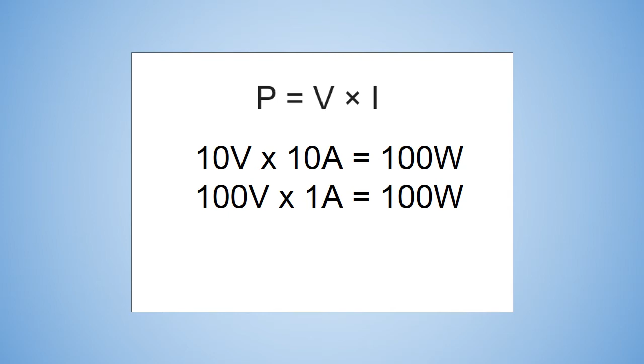But examine the V drop formula. A smaller current means a much smaller loss. Because current is a squared value, 1/10th the current means 1/100th the loss - 10 amps squared compared to 1 amp squared. Or 1/100th the current means 1/10,000th the loss - 100 squared compared to 1 squared. Raising the voltage and lowering the current has a huge effect.